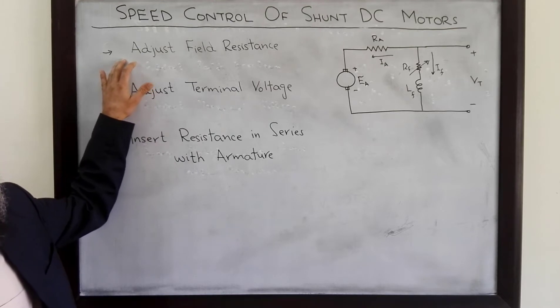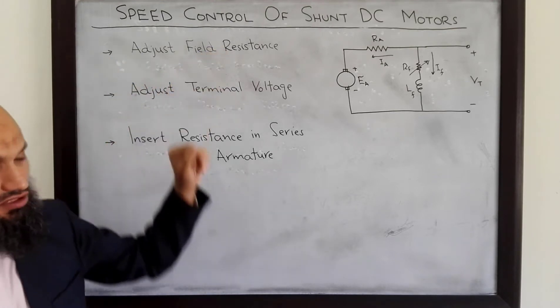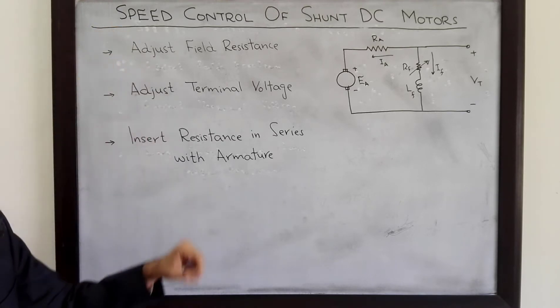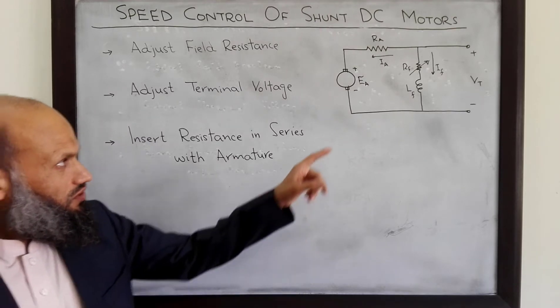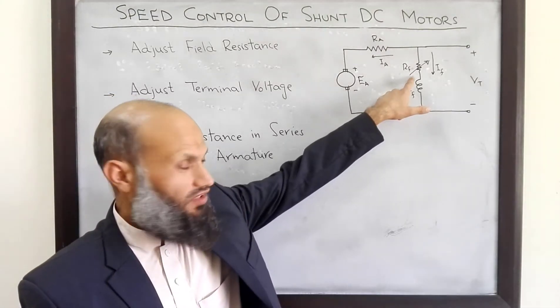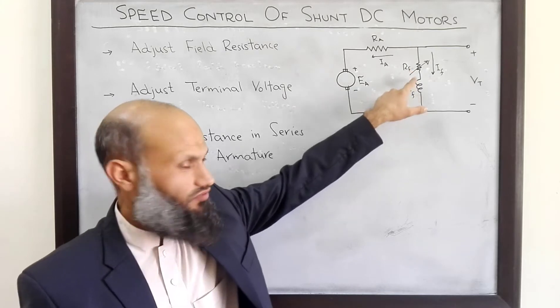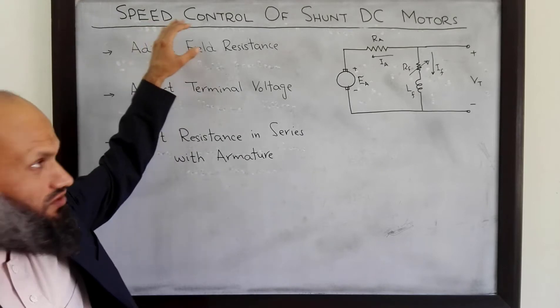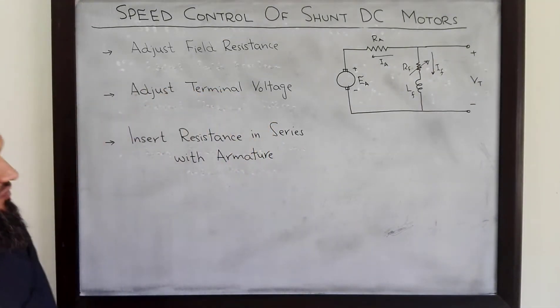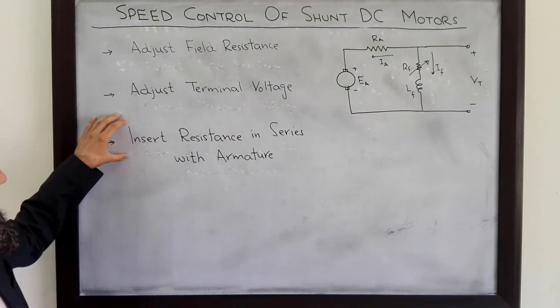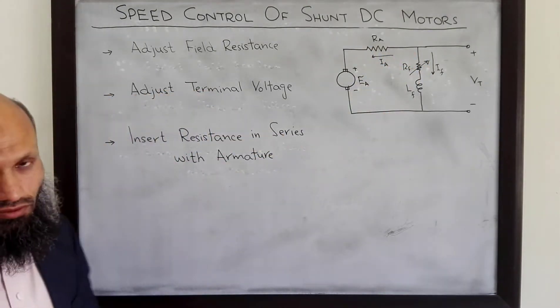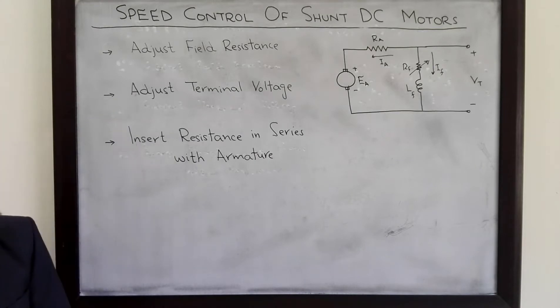Here are three different approaches that can be utilized to control the speed of a shunt DC motor. We can adjust the field resistance — there is a variable resistor inserted in series with the field winding that we can change to control the speed. We can also adjust the terminal voltage, and we may insert a resistor in series with the armature circuit as a third approach.